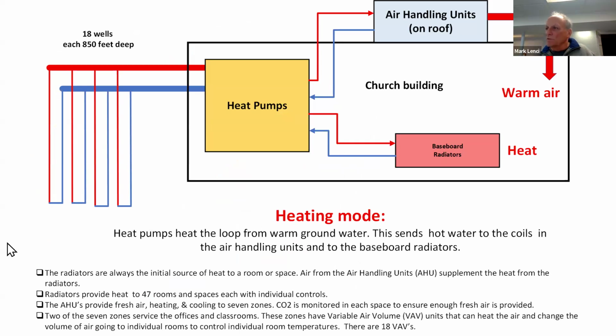This is the heating mode. You have your well field over on the left. The heat pumps take cold water out of the ground, heat it up, and hot water goes out to the baseboard radiators or up to the air handling units on the roof. The radiators radiate, and the roof air handling units send warm air down into the various zones, then it all goes back into the ground to get cooled down again.